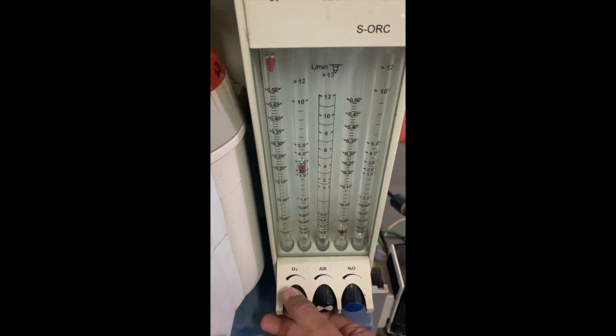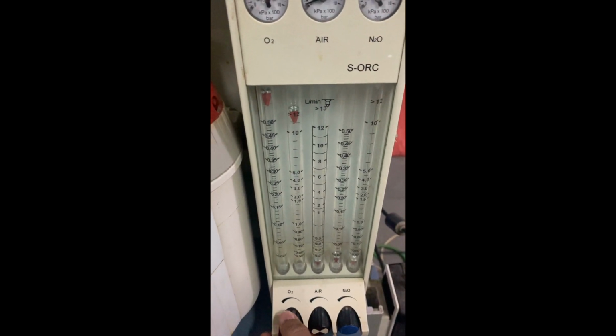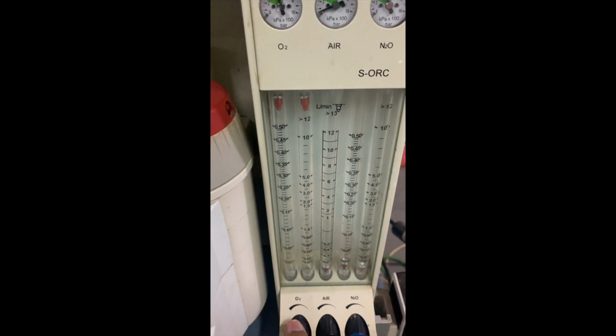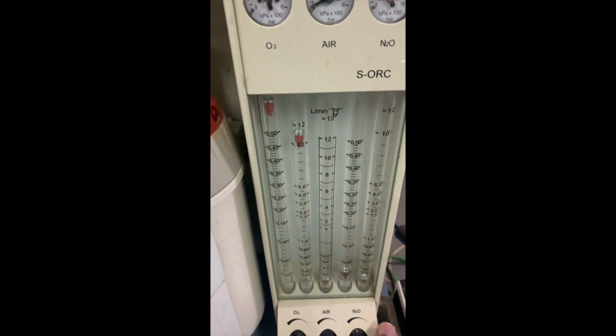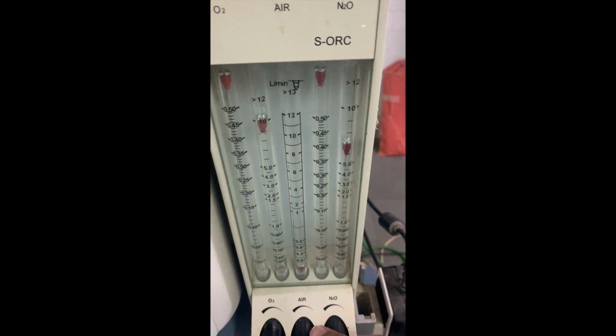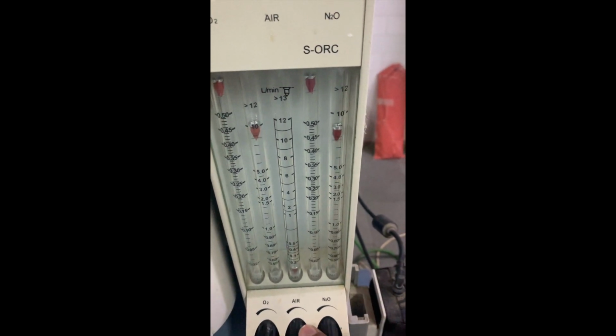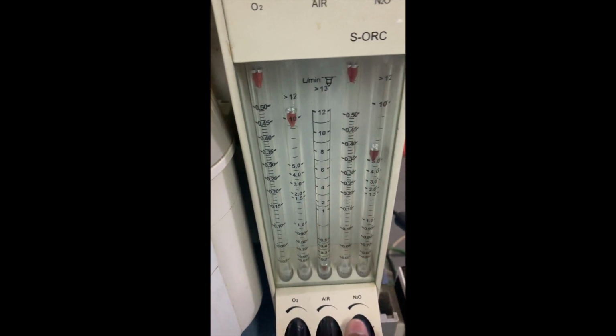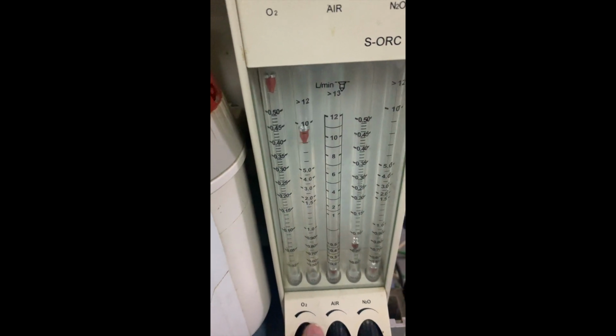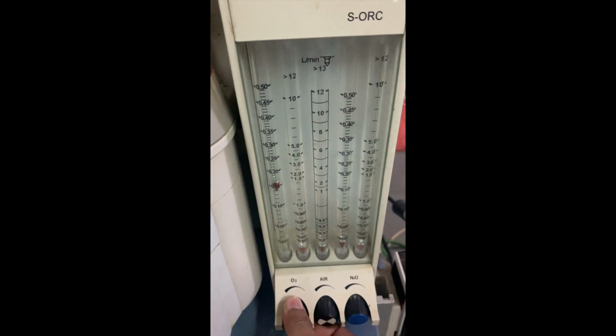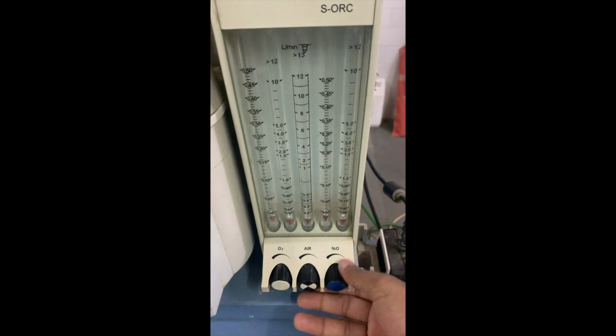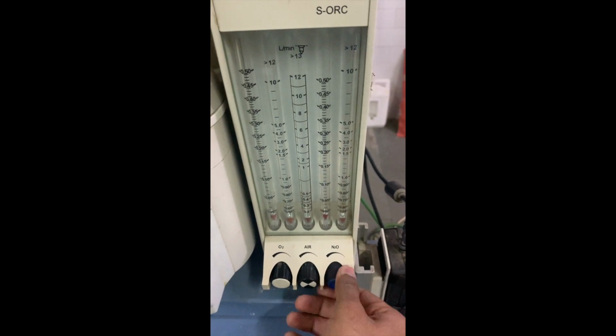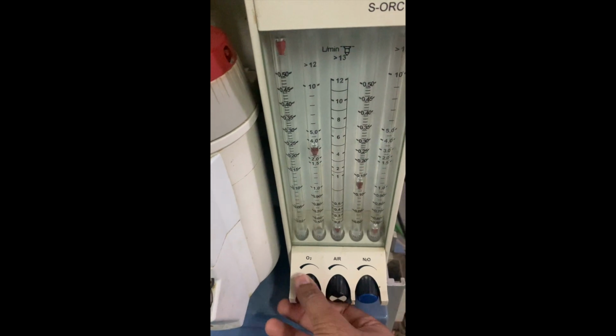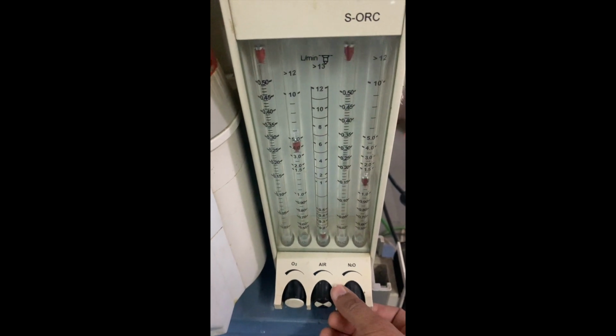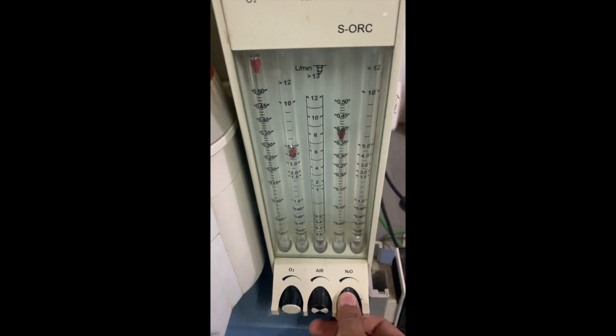Next, turn the master switch on and all the necessary electrical components. Check the flow meters. Adjust the flow of gases through their full range, looking for smooth operation of floats and undamaged flow tubes. Here we can see the proper functioning of the hypoxia prevention safety device. On only opening nitrous oxide, the gas doesn't flow, but it does flow when the oxygen is also turned on.